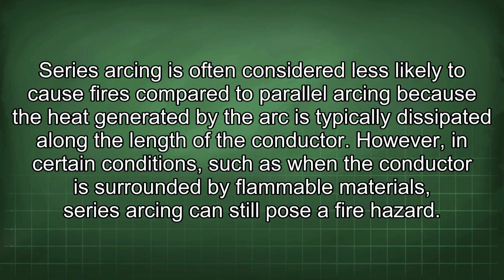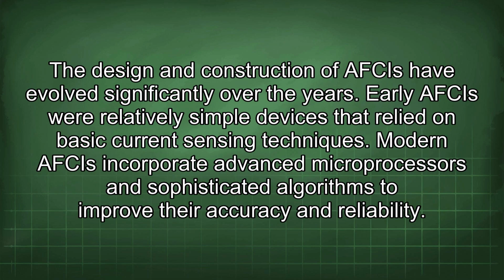Series arcing is often considered less likely to cause fires compared to parallel arcing because the heat generated by the arc is typically dissipated along the length of the conductor. However, in certain conditions, such as when the conductor is surrounded by flammable materials, series arcing can still pose a fire hazard. Design and construction of AFCIs have evolved significantly over the years.